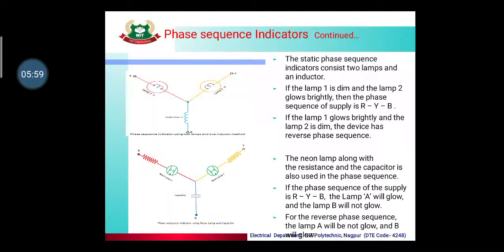The static type phase sequence indicator has no rotating parts — it remains stationary. It consists of two lamps and an inductor. Two lamps are connected to two phases and an inductor is connected to the third phase. If lamp one is dim and lamp two glows brightly, then the phase sequence of the supply is R-Y-B (correct). If lamp one glows brightly and lamp two is dim, the phase sequence is reversed.